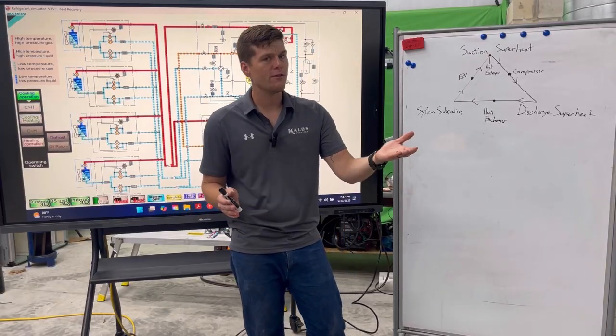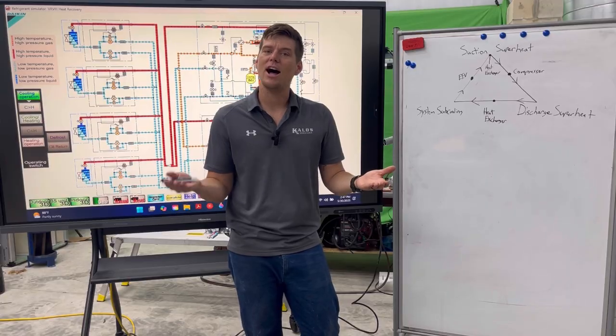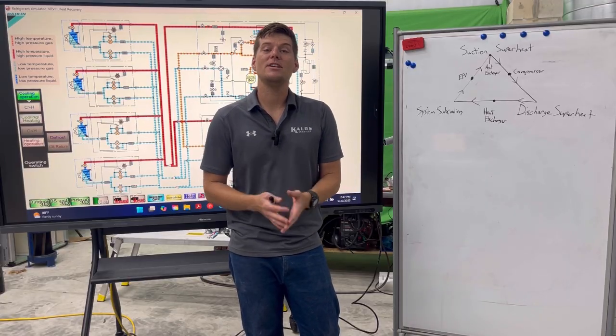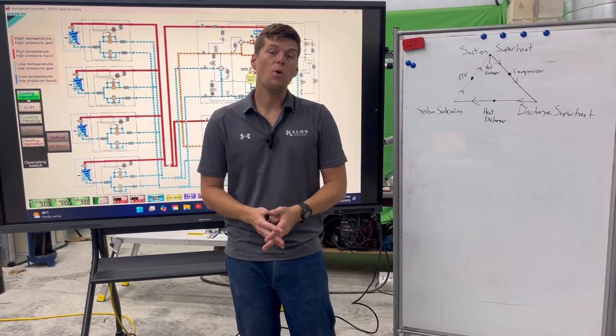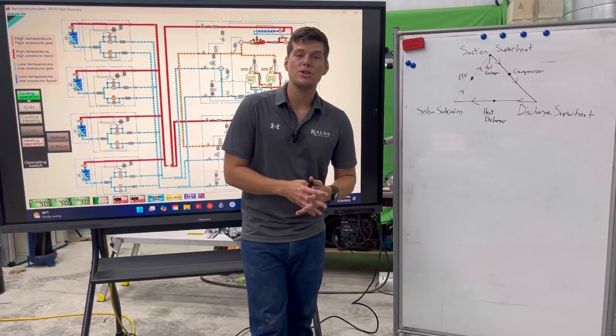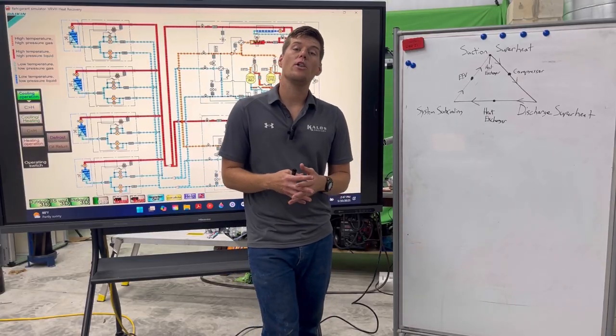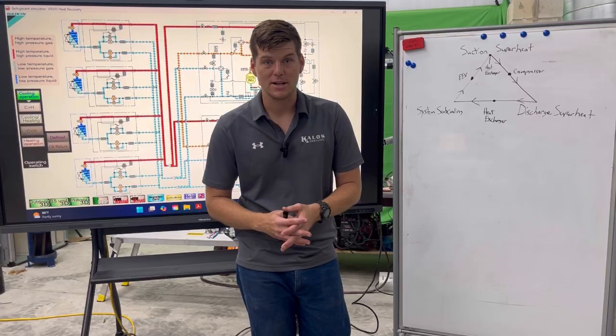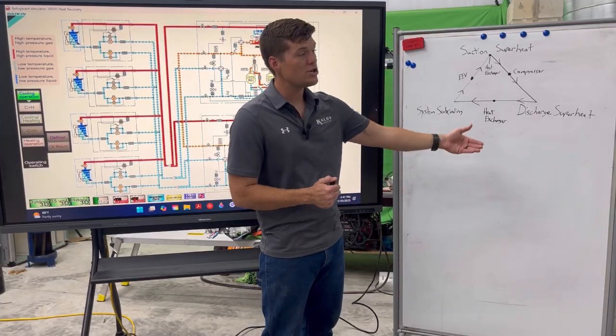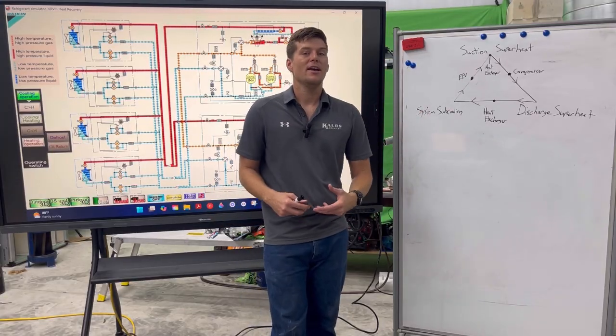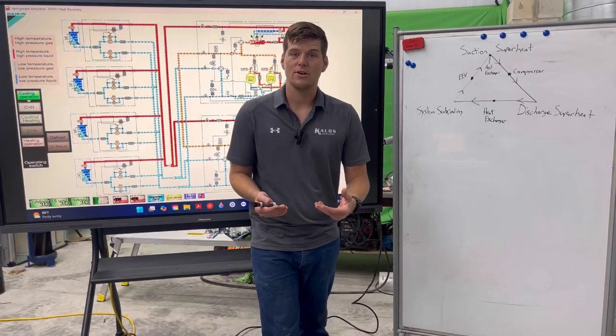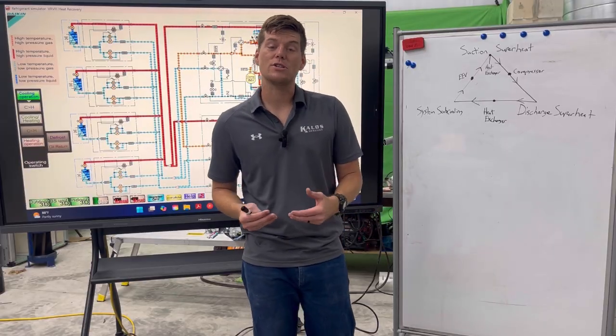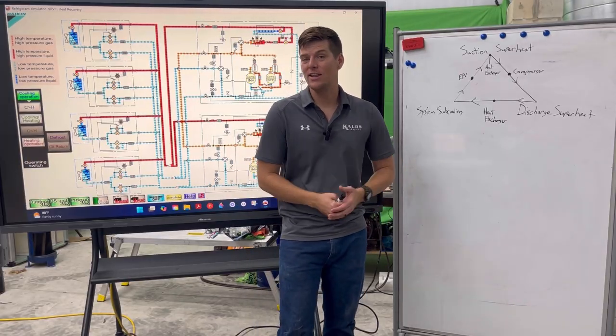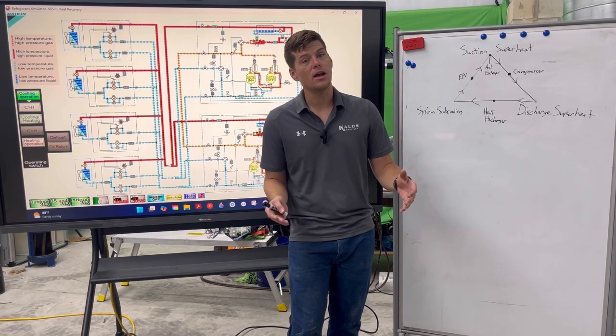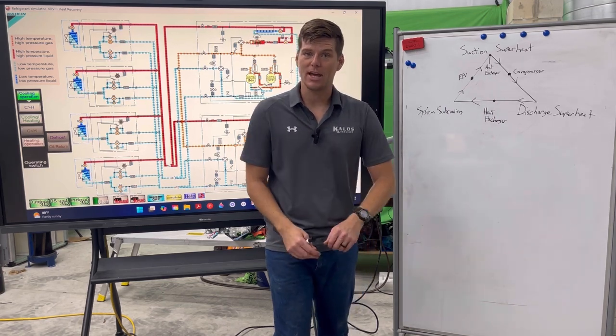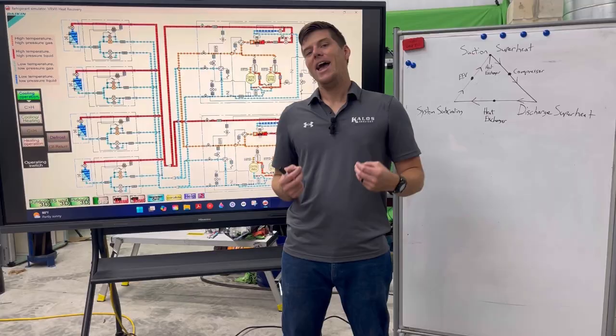If it's getting enough refrigerant, but my discharge superheat is still high, that tells me that there's probably not enough oil within that compressor, or that it's an unlubricated operation within that compressor. And again, no oil, or there's damage internal to that compressor, because there are modes of operation while it's running that show no oil returning back to the compressor, and it's wearing the compressor out. And of course, now it always has an elevated level of discharge superheat. Maybe not all the time, but there are periods where it is unlubricated. Those are things that we can measure as technicians.